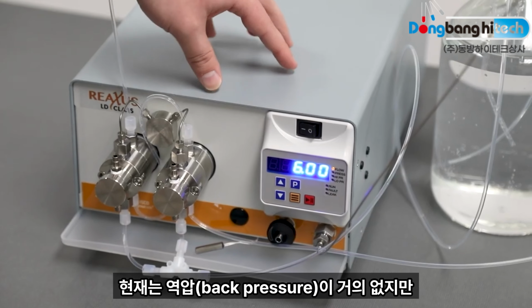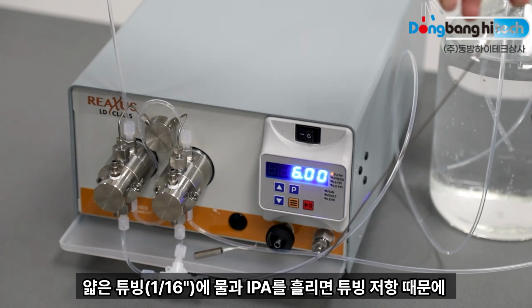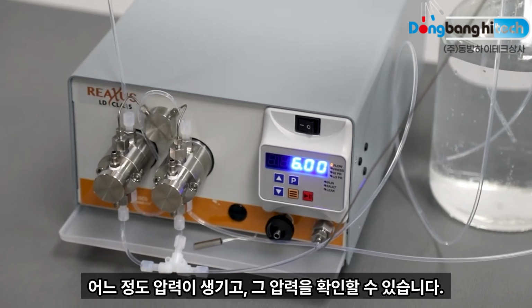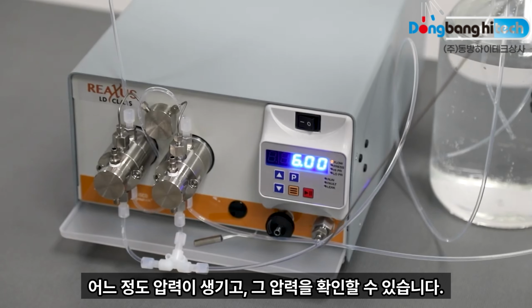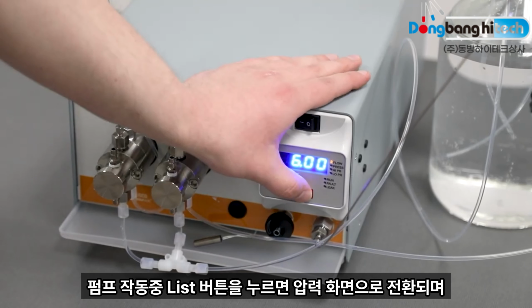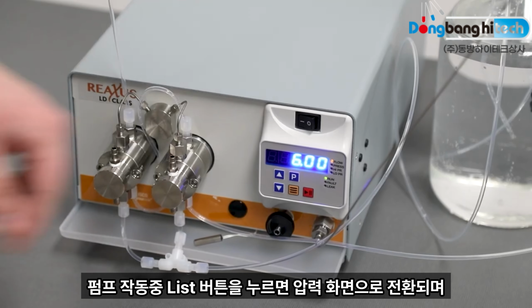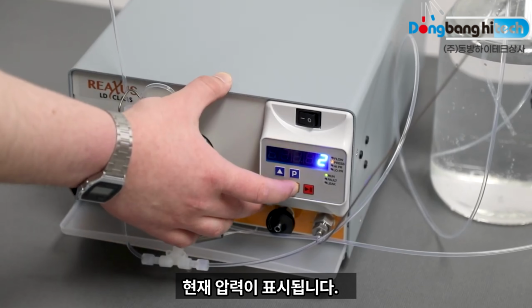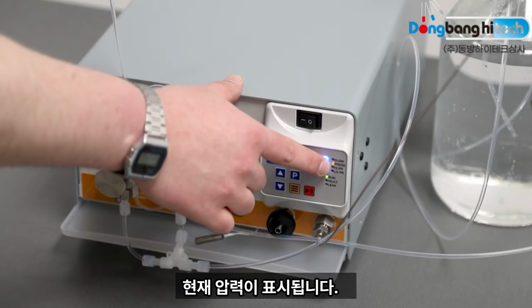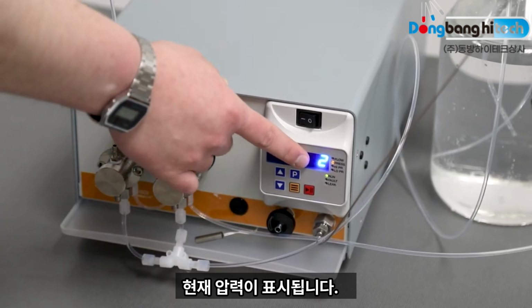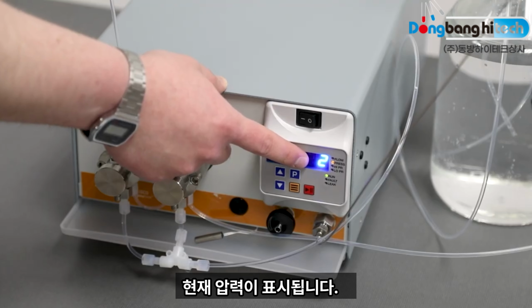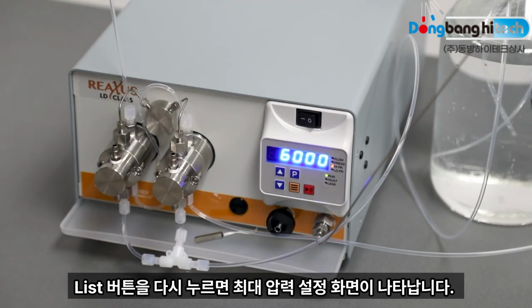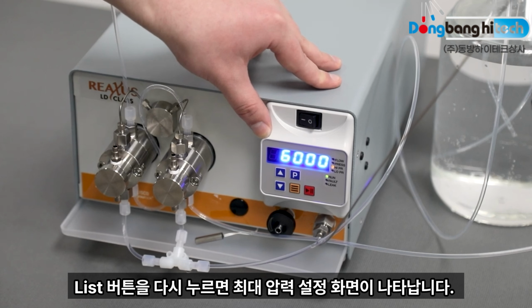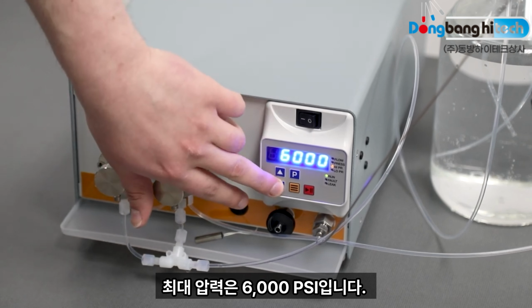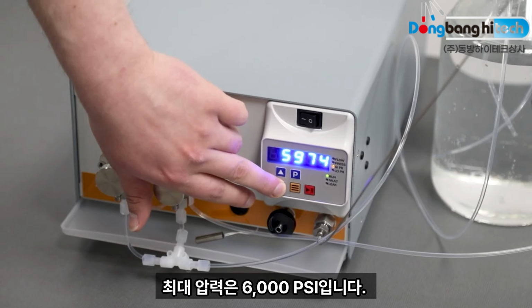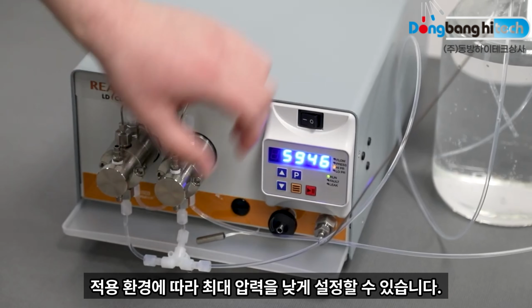We don't have any back pressure on the system currently, though since we are using 1/16 inch tubing with water and IPA, we will generate some sort of back pressure with the resistance. To check that back pressure, when I am running the pump, I can press the list button under our prime. This will now change our view to pressure, and I can see we're generating 2 psi worth of back pressure. If I press the list button again, I'll get my high pressure maximum. Maximum pressure is 6,000 psi, and I can decrease this depending on my application to set the maximum pressure.